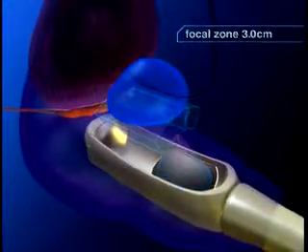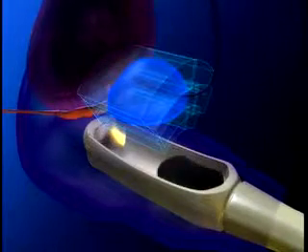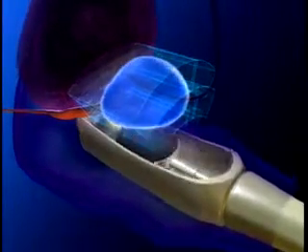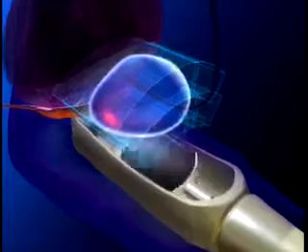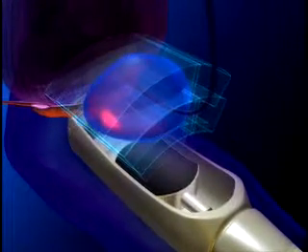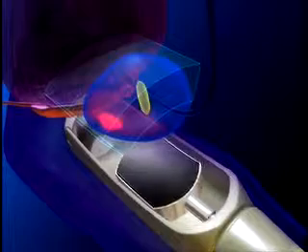The result is an accurate and repeatable lesion at the target sites that are monitored in real time by the treating physician. All the treatment zones are pre-planned and checked by the physician prior to starting the HIFU treatment.